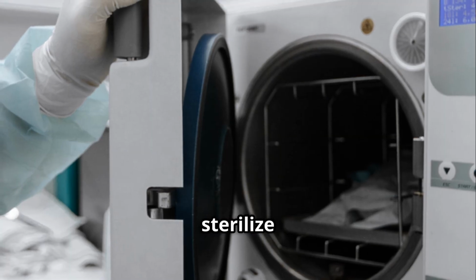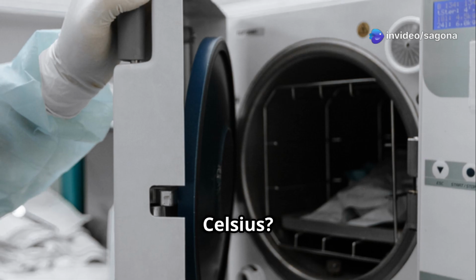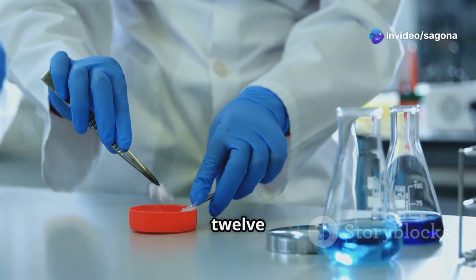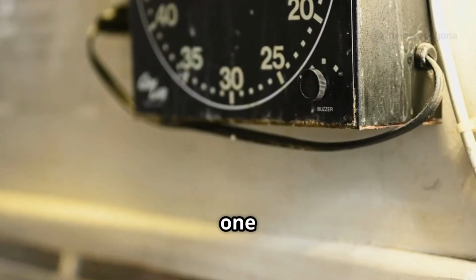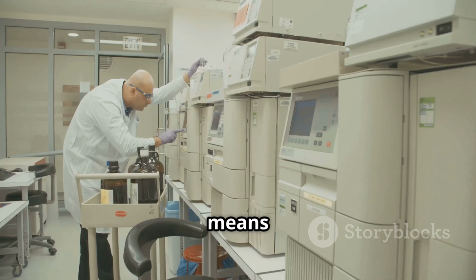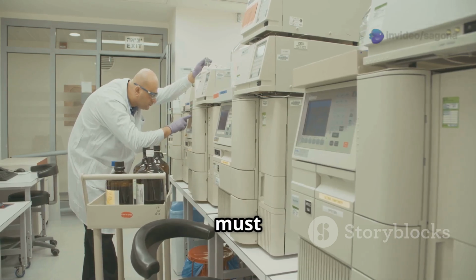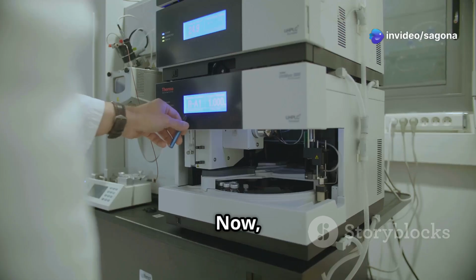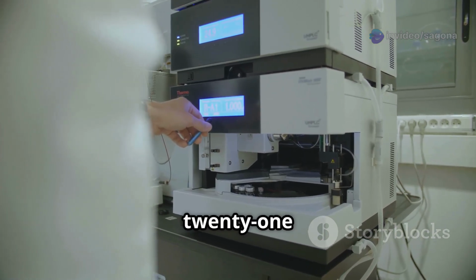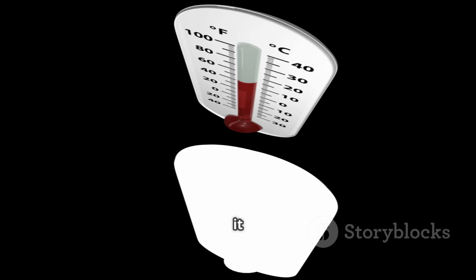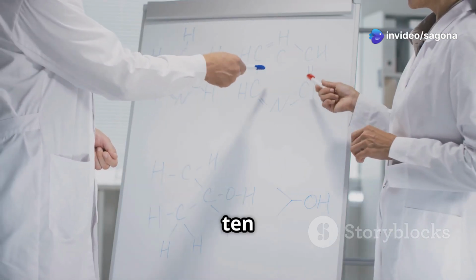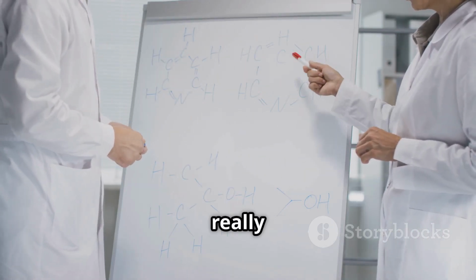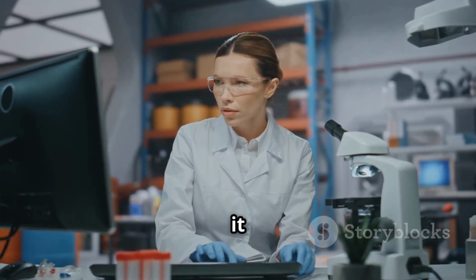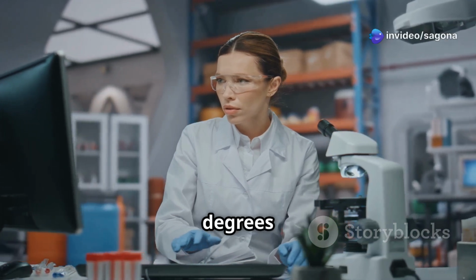So how long do they need to sterilize for at 121 degrees Celsius? They need to expose the medicine to heat for 12 times the D value, so that's 12 multiplied by 1 minute, which equals 12 minutes. This means their target F0 value for the autoclave cycle must be at least 12 minutes. This calculation is critical. Now, what if their autoclave doesn't hold exactly 121 degrees Celsius for the whole time? What if it runs a little hotter during some parts of the cycle, say at 124 degrees Celsius for a few minutes? This is where the Z value, which we said was 10 degrees Celsius, and the F0 calculation become really clever. The F0 value doesn't just count the minutes, it calculates the equivalent minutes at 121 degrees Celsius.